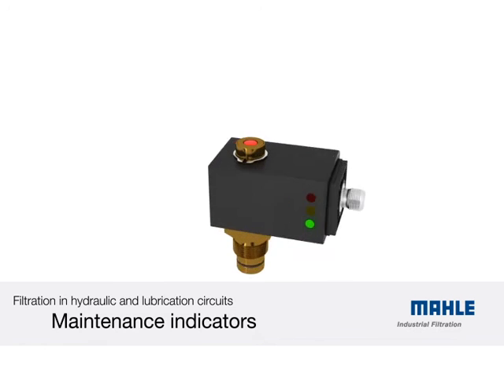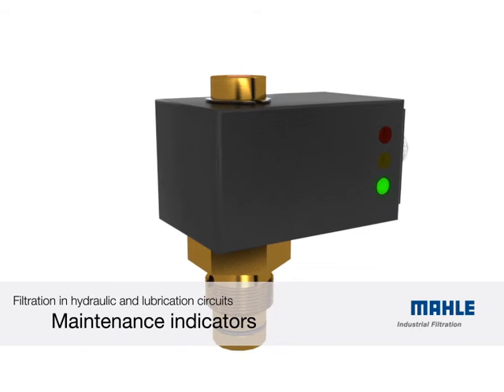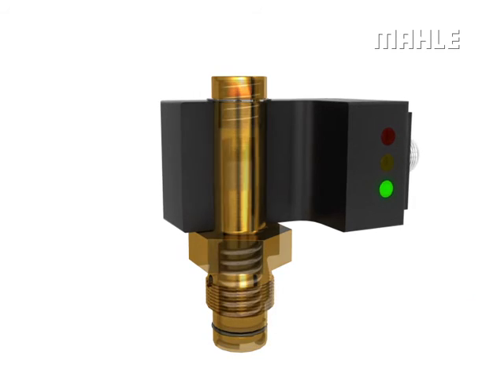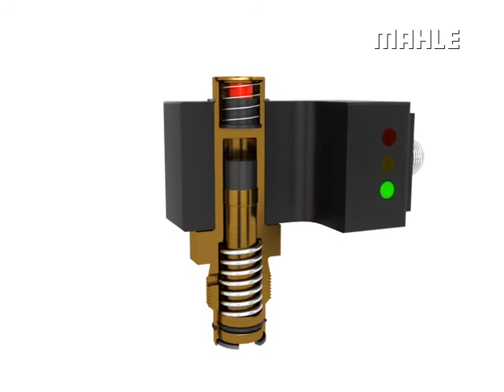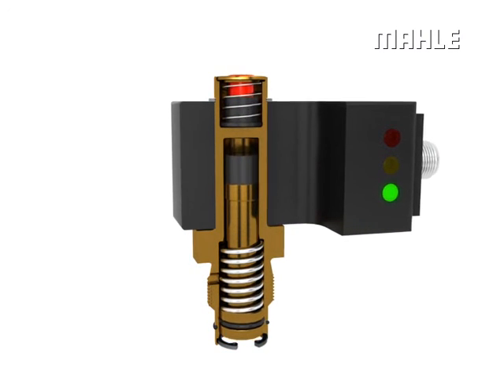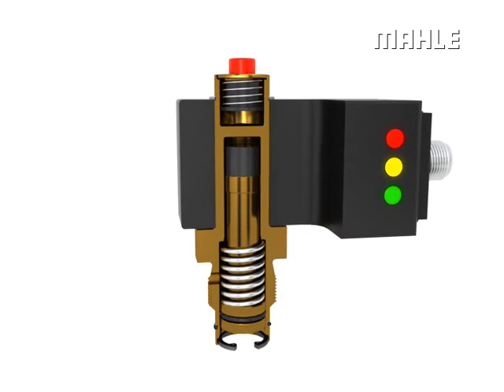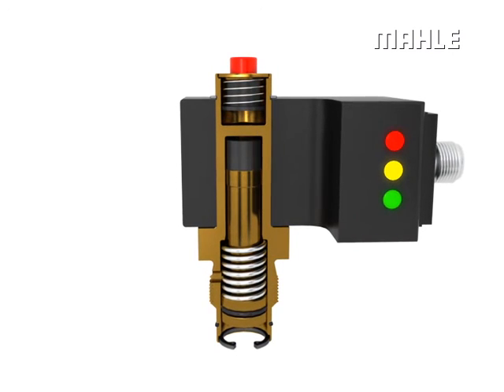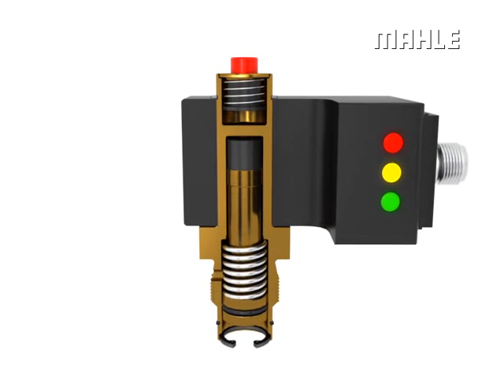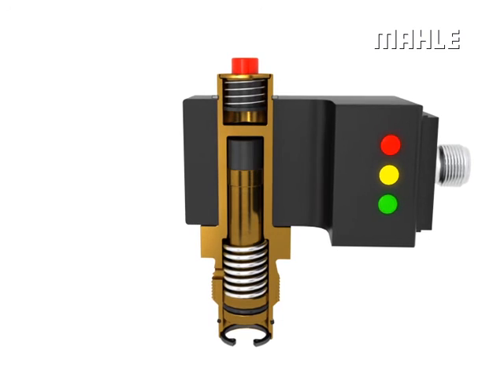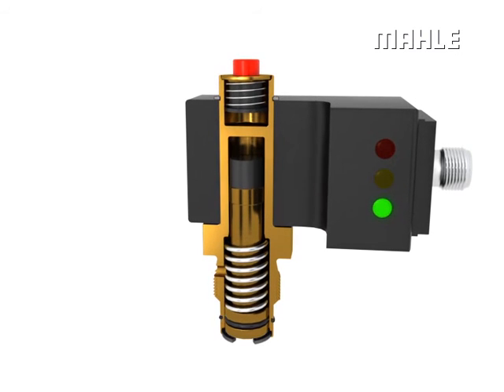Maintenance indicators enable the most cost-effective use of filter elements. When a filter element has been utilized to full capacity, the differential pressure increases. This increased pressure triggers a piston movement, which is then converted into an optical as well as an electrical signal.